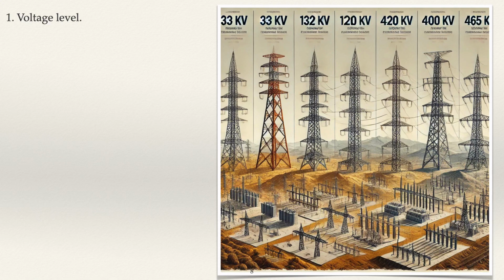Insulation requirements. Insulation ensures that the transmission line operates safely without electricity escaping into the surroundings or causing faults. Voltage surges. Insulation must be designed to handle fluctuations caused by switching operations, lightning strikes, or load variations. Environmental conditions. Humidity, temperature, pollution, and altitude can affect insulation performance. For instance, in humid or polluted areas, materials with higher dielectric strength and longer creepage distances are used. In high-altitude regions, reduced air pressure may require additional insulation. Insulation and clearances between conductors and between the conductor and the ground or structures must comply with safety standards to prevent flashovers. By carefully selecting the voltage level and ensuring adequate insulation, designers create transmission systems that meet both technical and regulatory standards, ensuring efficiency, safety, and longevity of the infrastructure.